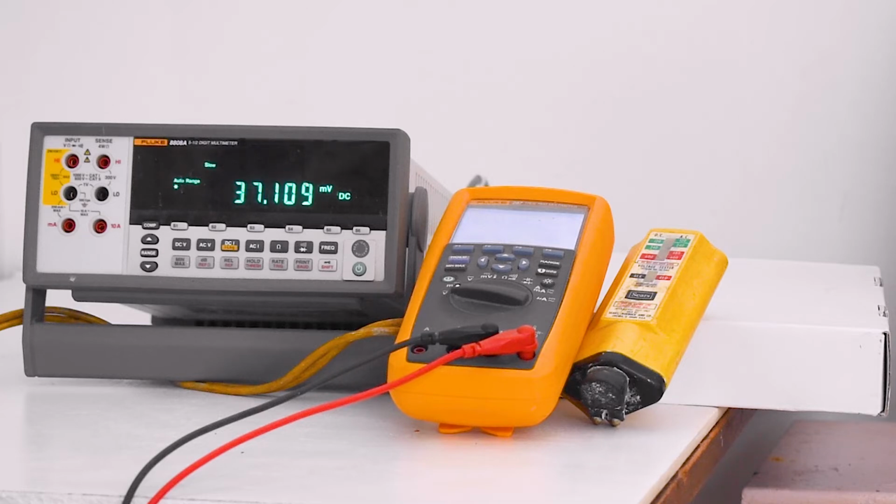The Fluke voltmeter is a high impedance instrument, meaning that the input circuit through the probes draws very little current from the source. We say that it does not load the circuit under measurement. The voltmeter is invisible. That is appropriate for sensitive electronic circuits, which would be disrupted, if not destroyed, by the greater amount of current imposed by a low impedance instrument.